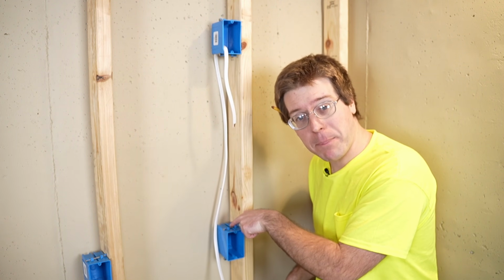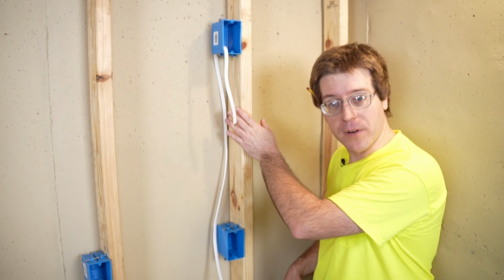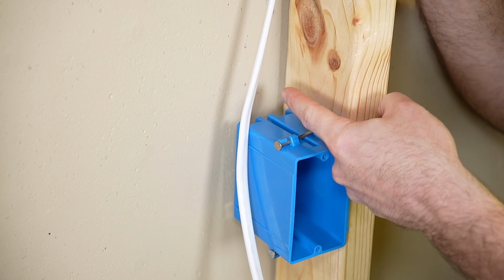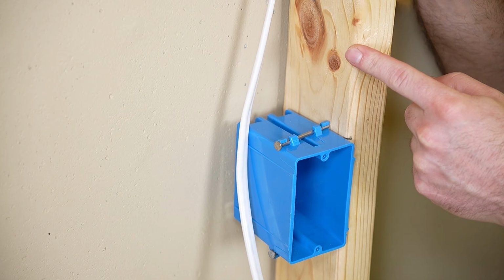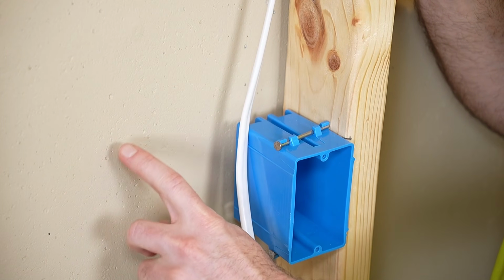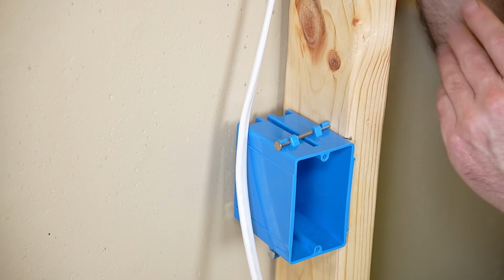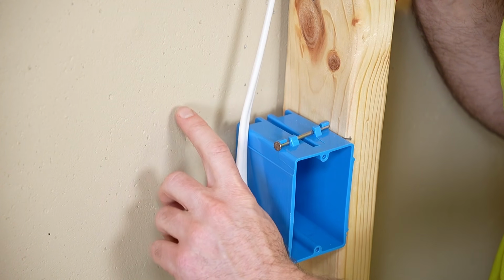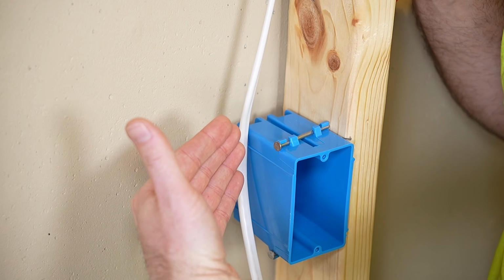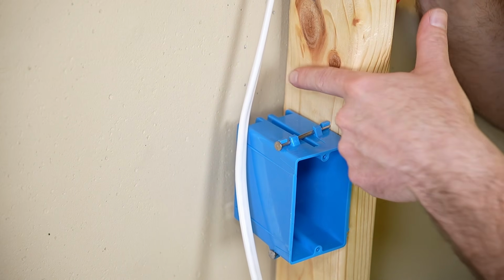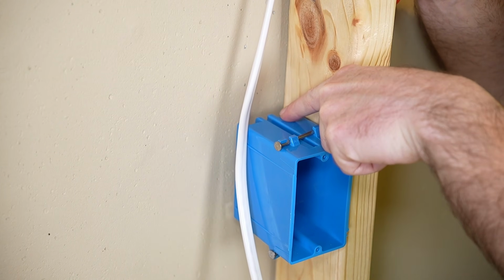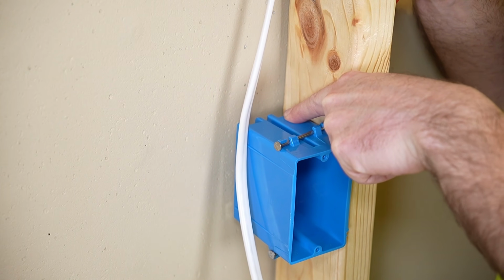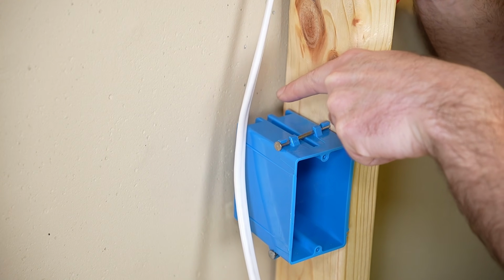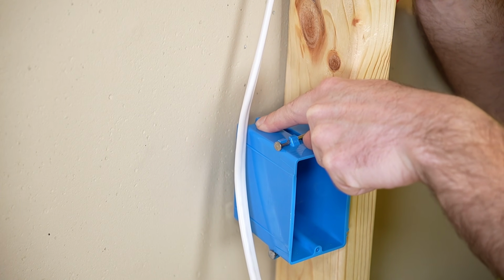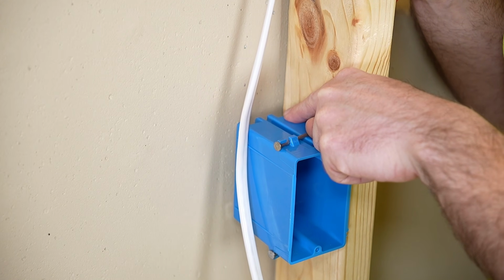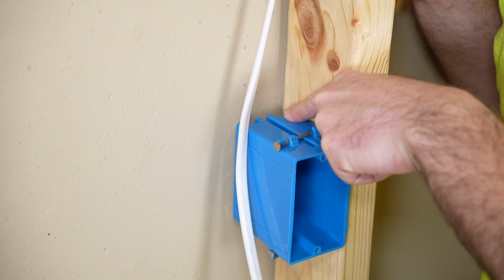Now we can come in the top of this box with this wire going up from it. We do not want to use the knockout that's close to the stud. The reason is, when they install sheetrock, imagine there wasn't a concrete wall behind this stud wall—maybe this stud wall is in the center of a room, with sheetrock installed on the back as well. When the sheetrockers install their screws, if they go in at an angle, there's a good chance that screw will hit the wire entering the box right here. So we need to use the farther knockout instead, never the one closest to the stud. You're probably asking, why does that closer knockout even exist then?